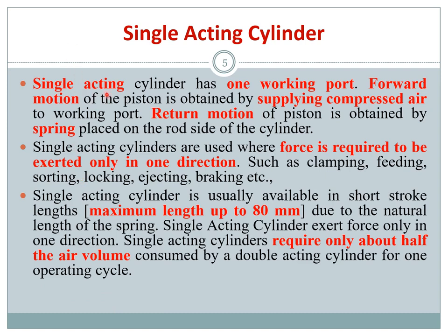A single acting cylinder has one working port — compressed air enters at one particular side and the return motion is controlled by the spring. Forward motion is obtained by supplying compressed air, which extends the cylinder. Once pressure is removed, the spring returns the piston to its original position.